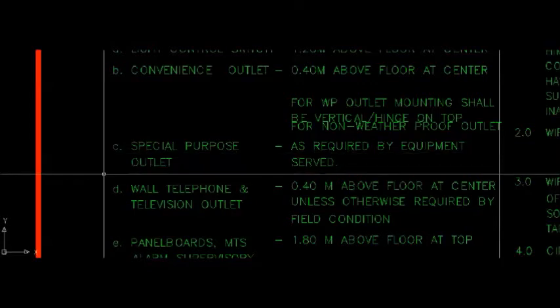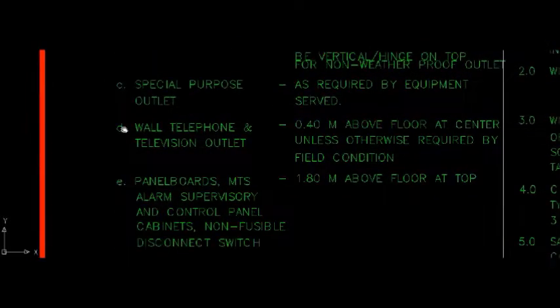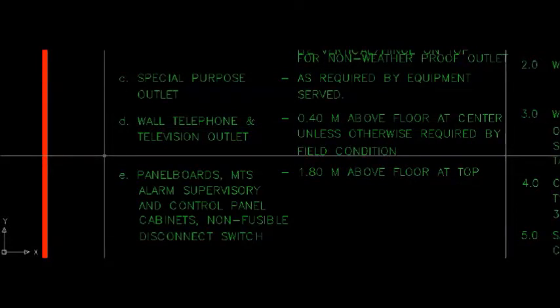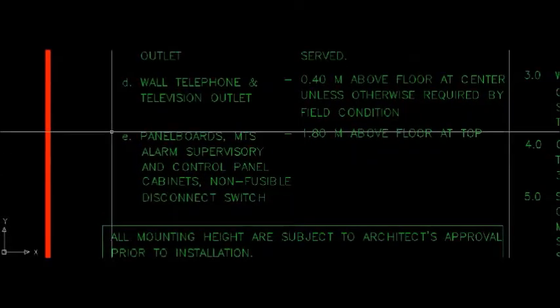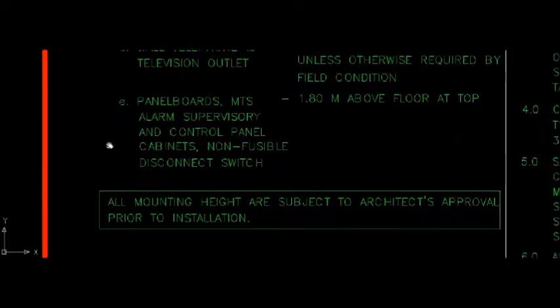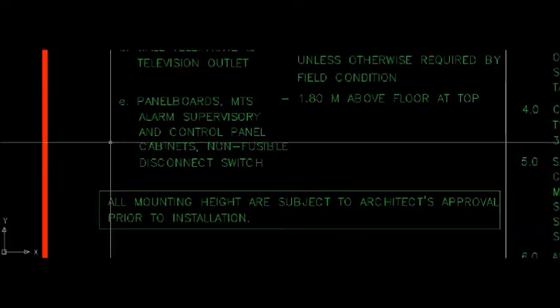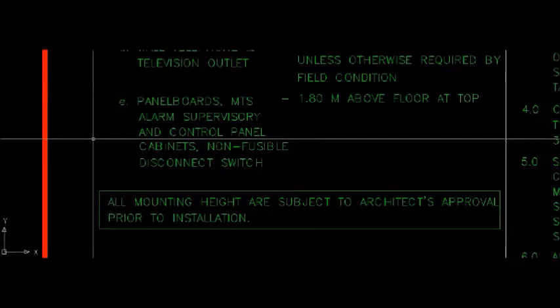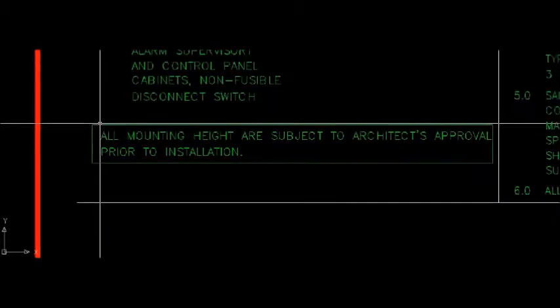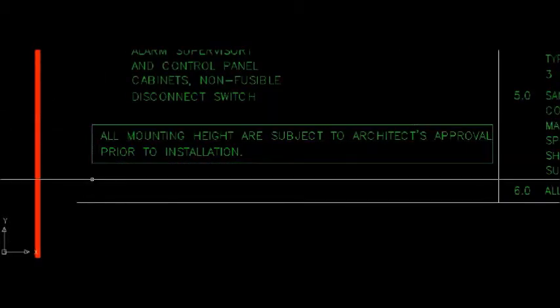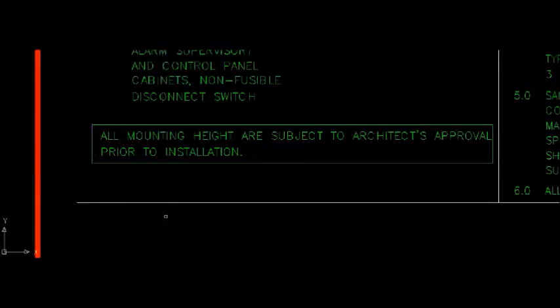For WP outlet, mounting shall be vertical, or hinged on top for non-weatherproof outlet. Special purpose outlet, as required by equipment served. Wall telephone and television outlet, 0.40 meters above floor at center unless otherwise required by field condition. Panel boards, MTS, alarm, supervisory and control panel, cabinets, non-fusible disconnect switch, 1.80 meters above floor at top. All mounting heights are subject to architect's approval prior to installation. Legend.